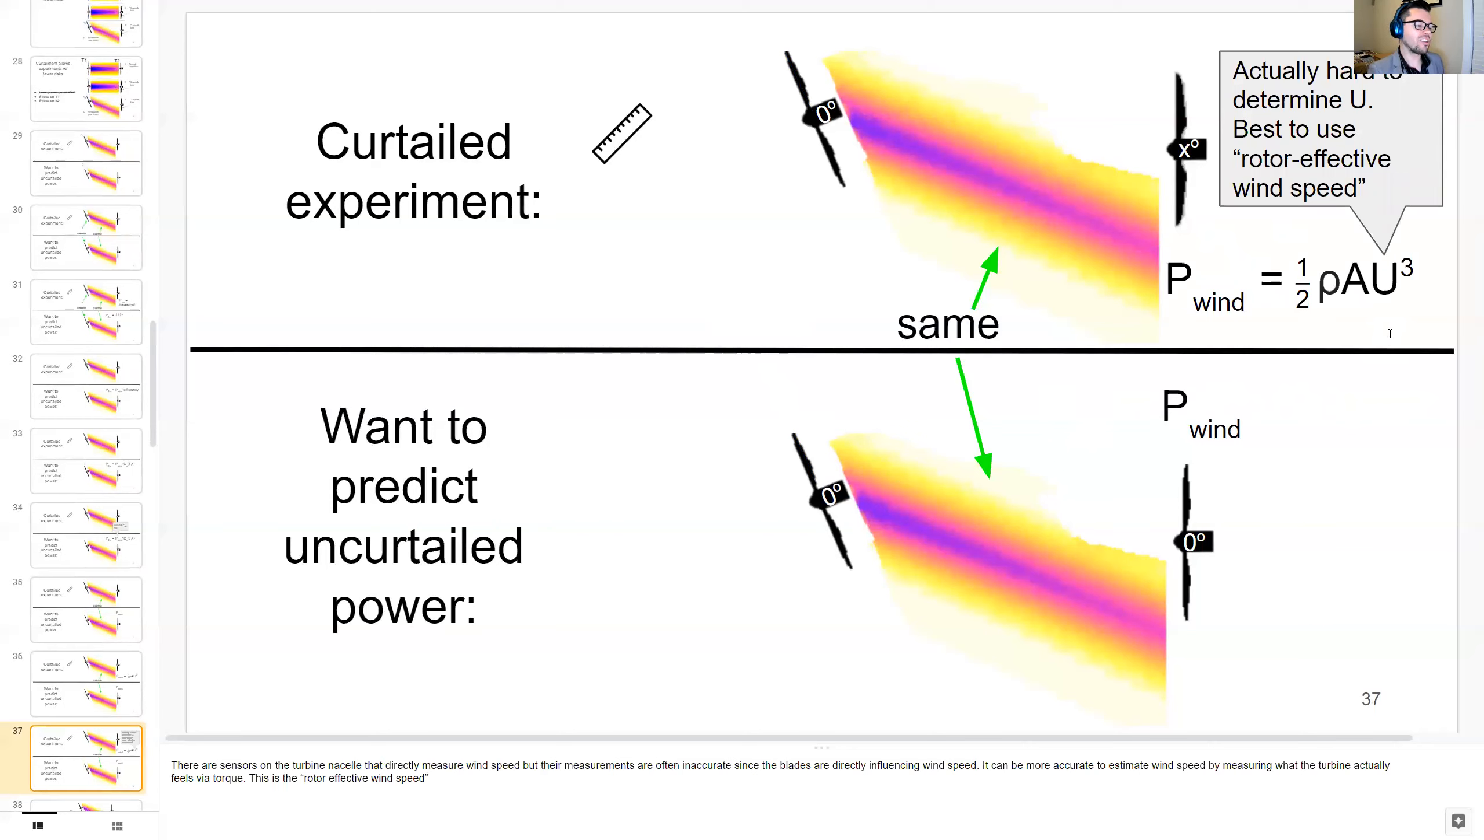There are sensors on the turbine nacelle that directly measure wind speed, but their measurements are often inaccurate since the blades are directly influencing wind speeds. It can be more accurate to estimate wind speeds by measuring what the turbine actually feels via torque. This is called the rotor effective wind speed.